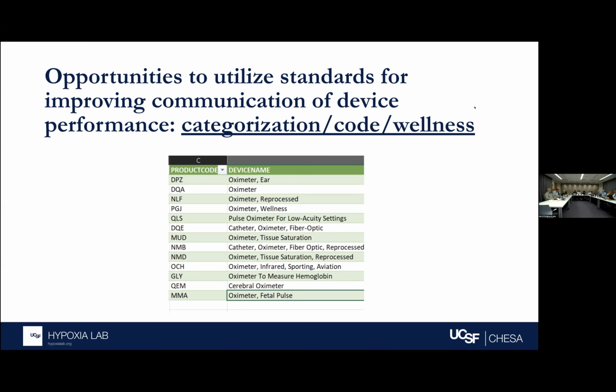So I think the comments regarding product codes, just for clarity on this slide, these are all the product codes in a particular regulation. And I'm sorry if this is a little bit wonky, but that's CFR 870.2700. Those are basically the basic technology functional type of bucketing that the agency did for now several decades. And these devices are all light-based oximeters. There are only a handful of them that you would be familiar with in the context of oximetry and getting a SpO2 number. And just to be clear, DQA is the product code in which most of these fingertip pulse oximeters would be sitting. Those are prescription use types of devices for medical purposes, and the commensurate standards and testing would apply.